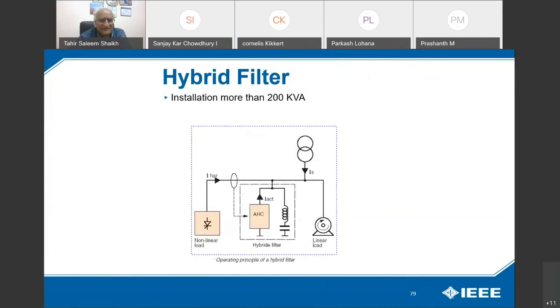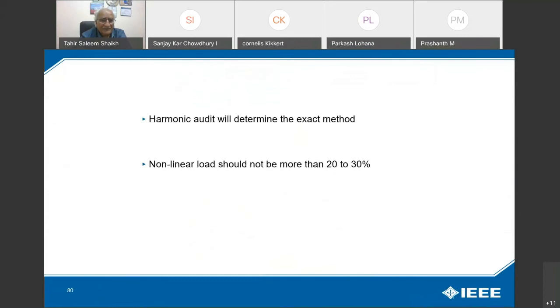This installation is for more than 200 kVA, with a hybrid filter. It is a combination of the active sine filter as well as the passive filter. Whatever remains with the active sine filter, this hybrid filter will correct with a sensing device to create the same harmonics, which will nullify the impact of the harmonics on linear loads. So this is for installations of more than 200 kVA. Whenever you have to decide, a harmonic audit will determine the exact method. As a general practice, nonlinear load should not be more than 20% of a transformer or generator.